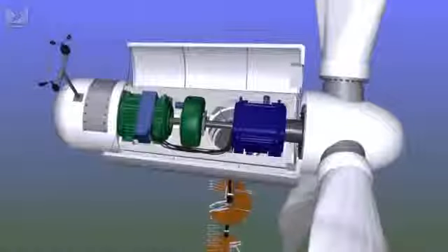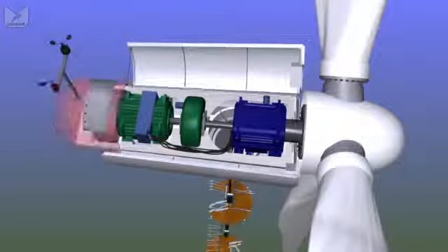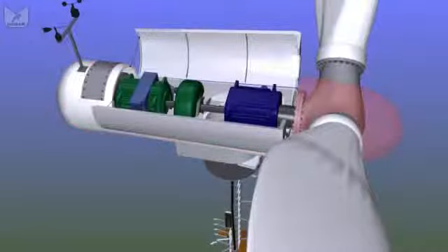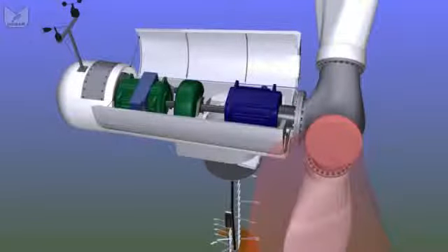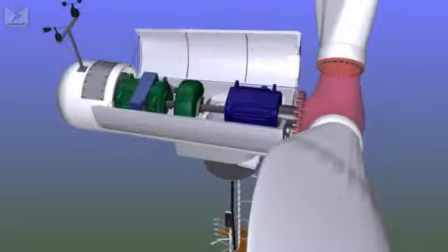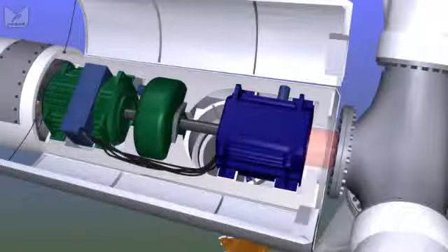And the nacelle in this case is a vaguely tapered tube. At the back we have the wind sensors, which give us speed and direction and allow the turbine to face into the wind and to change the angle of the blades. The nacelle itself is just a fiberglass tube. At the front we have a similar fiberglass cowl protecting the hub, which is a steel casting on which we have bolted our three blades, and the blades can turn or pitch so that the angle they form with the wind can be varied.